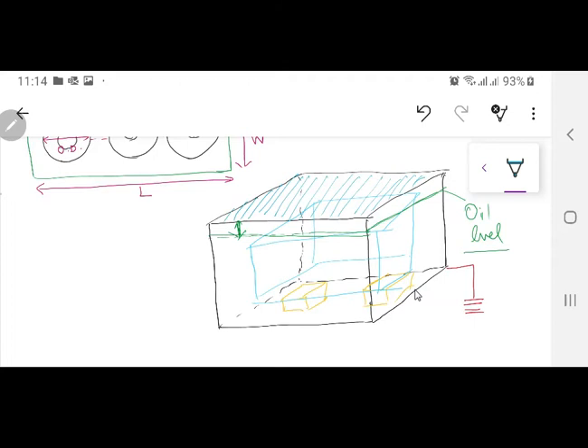Oil is not even in contact there. Secondly, the floor of the transformer tank always has cold oil near it, so heat won't dissipate from there either. So the actual or effective surface area of the tank which is going to dissipate the heat is just the four sides.